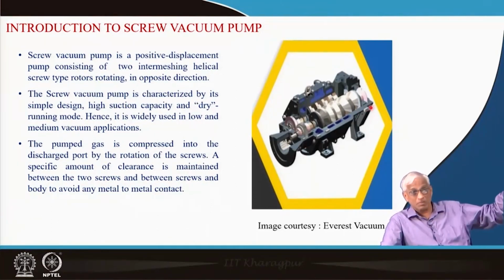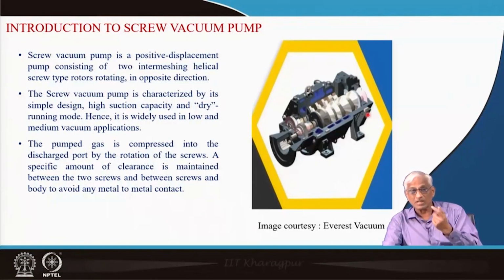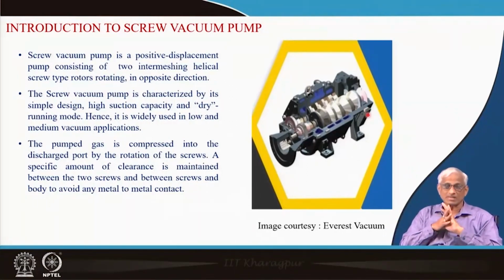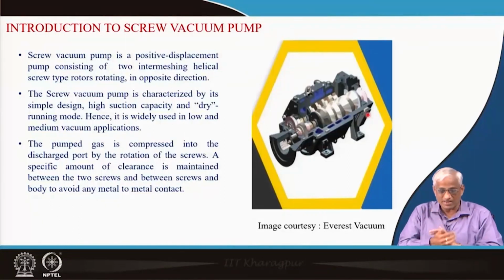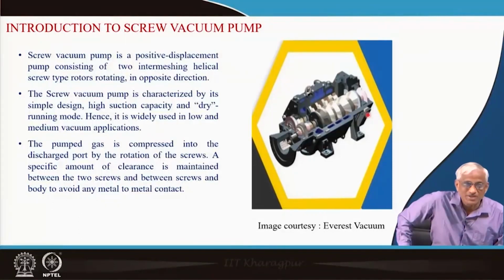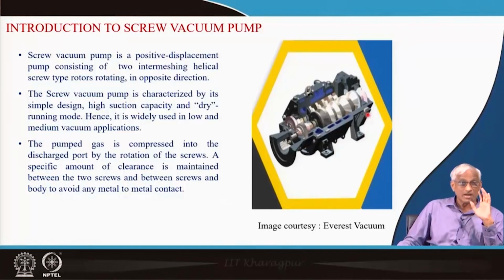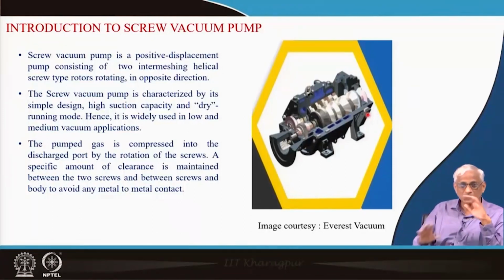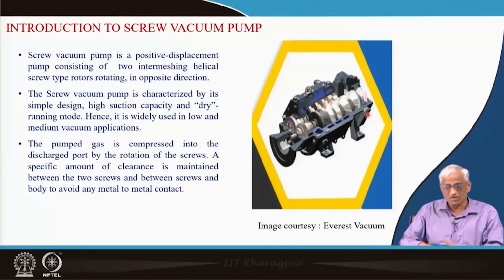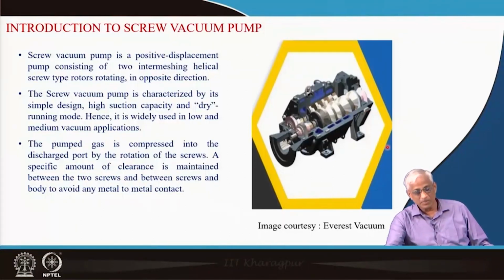You need to take care of heat of compression, etc. Sometimes hot vapors come from the process, so you have to be careful. The screw vacuum pumps have to operate under adverse conditions also, so you have to take care of all these precautions while designing the bearings and various assemblies like seals.